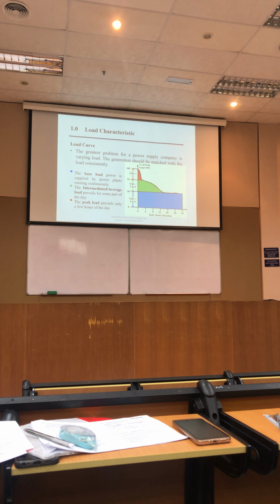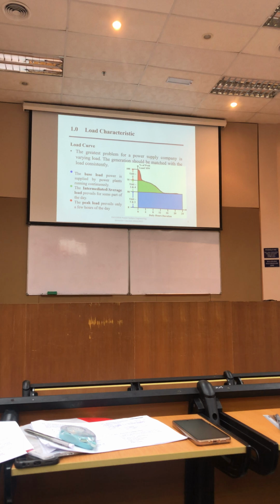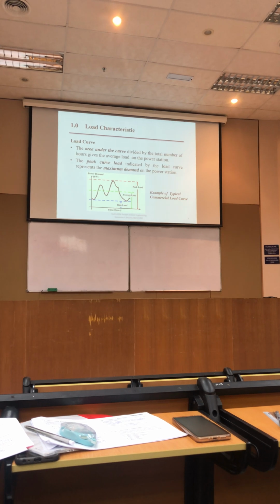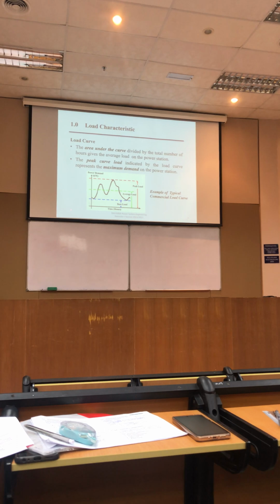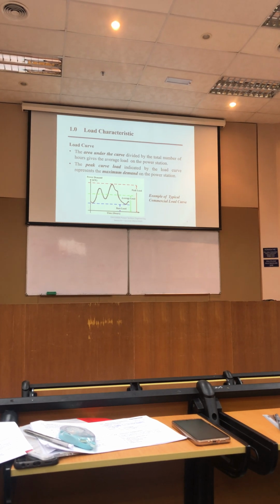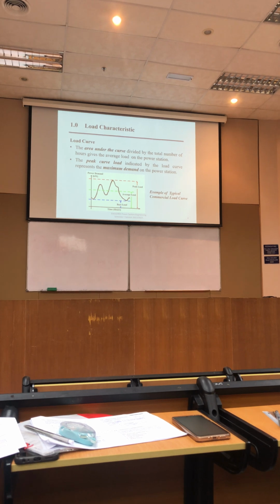So normally we are going to have many units. For example, 150 megawatts. Okay, so for example, for this case, it has 5 generators. For example, student, 150 megawatts, we have 5 generators. So for baseline, for base load, okay, so this one is what we call as base load. At any time, our power station must be able to supply this load 24/7. It means that at all time we must produce this base load.